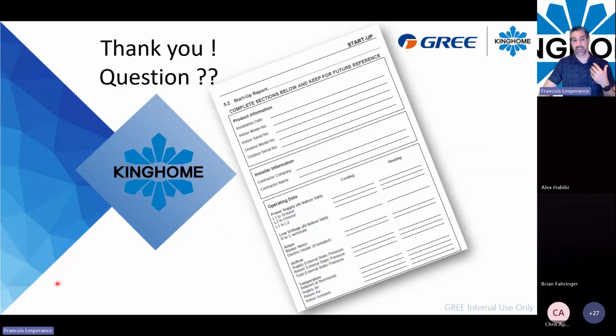Make sure you complete the startup report sheet correctly. That will help if you have to call for support. We are just a phone call away, but if you can give enough information on what you have in front of you and what you've done, like the airflow setting, the return air and supply air temperature, your dip switch configuration, your power voltage, all of that, it will be very helpful. Have this startup report sheet with you when you are on a call with the support tech.